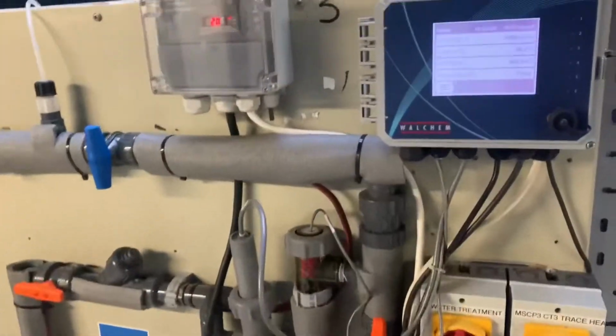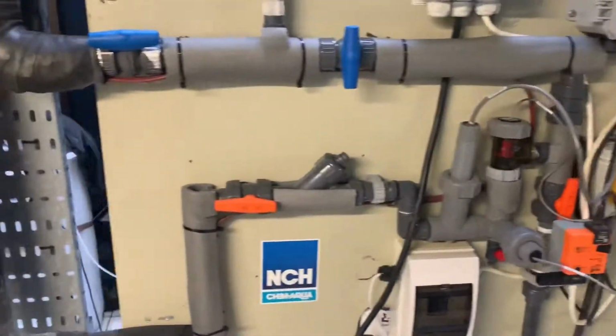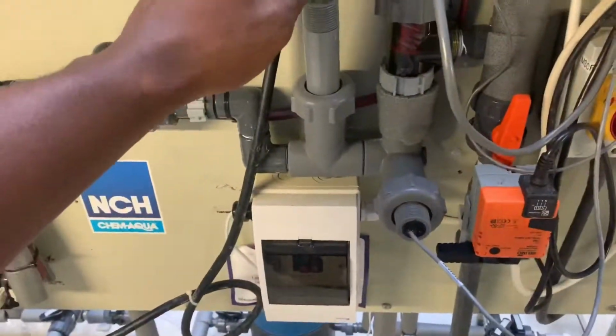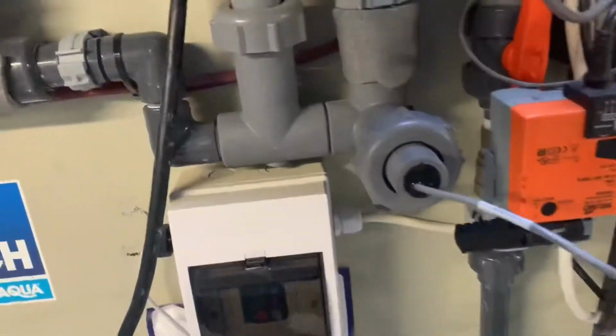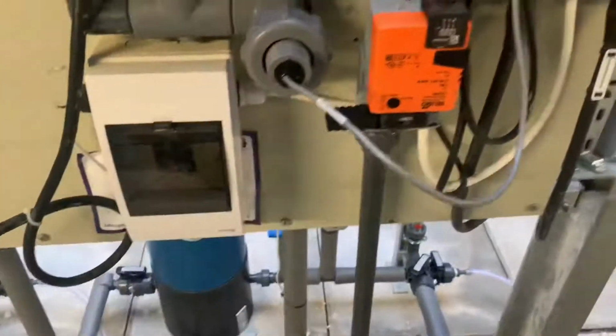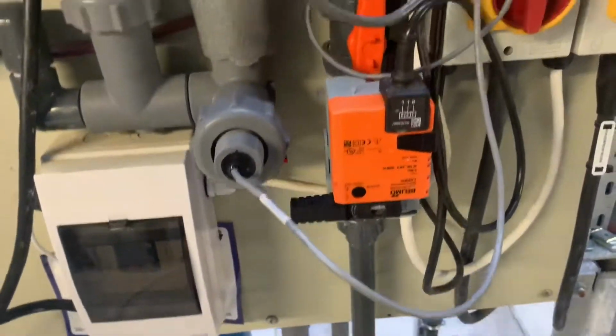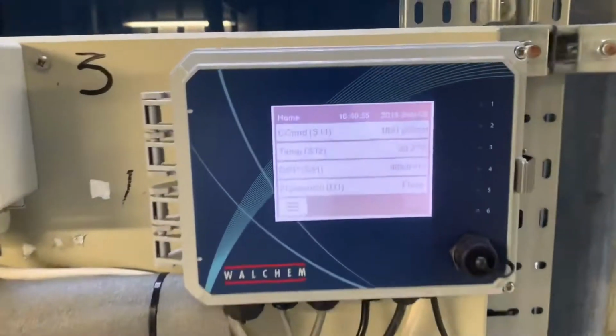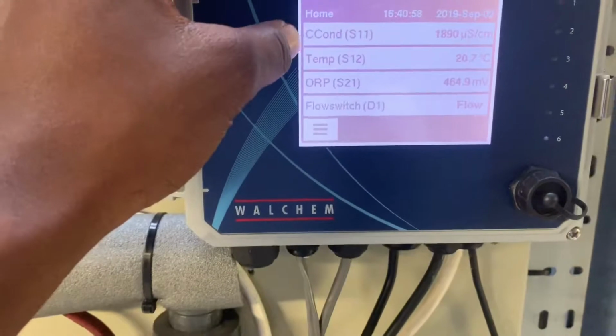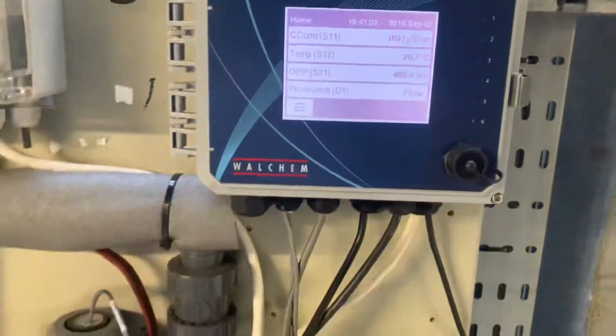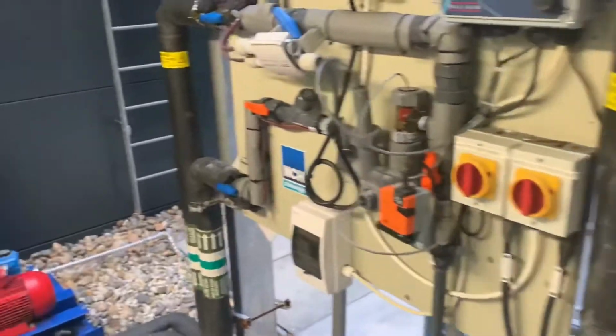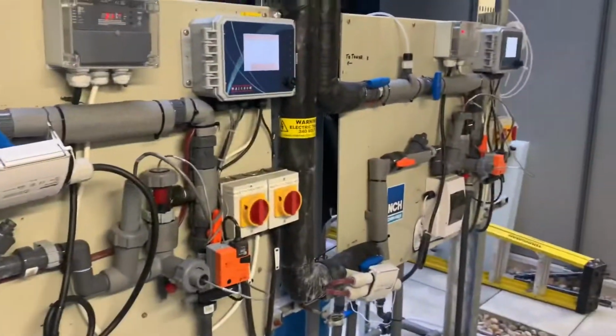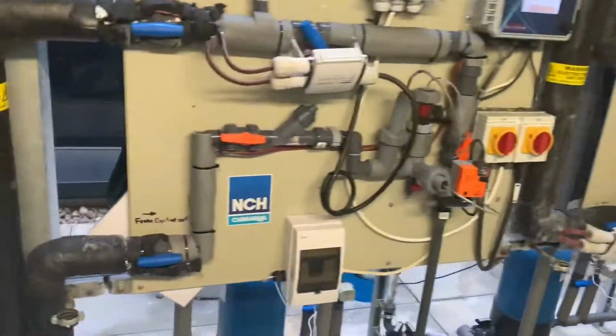So, let's swiggle the camera around and let's go to the manifold. So here we have our manifold, and it's made up out of valves, which are here, strainers, which are here, more valves. It's made up of probes, which are here, a flow reader, which is here, another probe, and an actuator, which opens and closes when we need to dump water. And this is our digital dial, which actually will tell us our conductivity and how many millivolts we have in our water, and all types of little stuff like that. So that's just the beginning to the tour, and this part is going to be about water treatment.